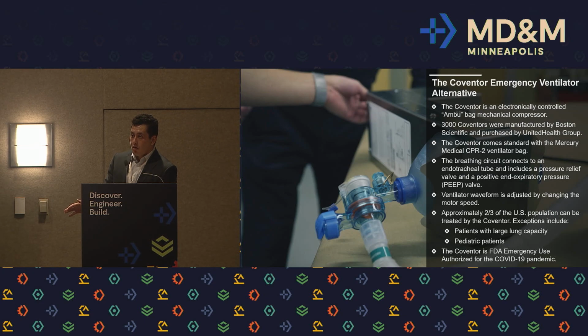It comes standard with a Mercury Medical CPR2 ventilator bag. The breathing circuit, as Steve mentioned, connects to an endotracheal tube, which is exactly the same as you would find on a normal ventilator. It also includes a valve for positive end expiratory pressure, which is PEEP. This helps maintain the blood oxygenation level and helps clear out the CO2 in the blood. It also includes a pressure relief valve for safety.